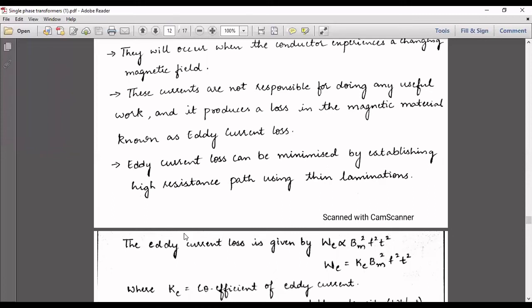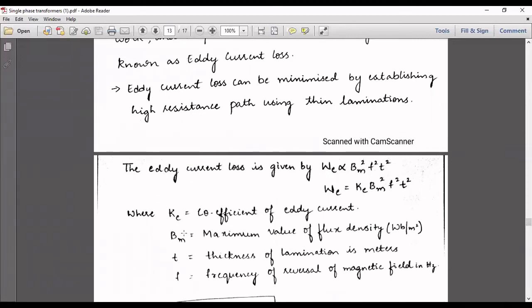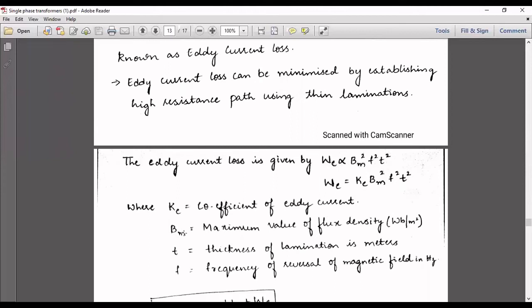So the eddy current loss is given by WE directly proportional to BM square F square T square. Because it involves the resistance and current values, all the values are taken in square. So WE is equal to KE into BM square F square T square, where KE is the coefficient of eddy current, BM is the maximum value of flux density, given in Weber per meter square, T is the thickness of lamination in meters, and F is the frequency of reversal of the magnetic field in hertz.